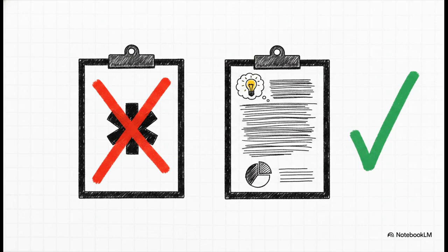Now, when you finally make these decisions, please don't just file away a final score, like a risk priority number, and call it a day. Two identical scores can mean vastly different things in reality. The true value of this entire exercise lies in documenting the rationale. Record exactly why you chose that score, cite the data you used, state your assumptions, and explain why the control is proportionate. The reasoning is what really matters here.